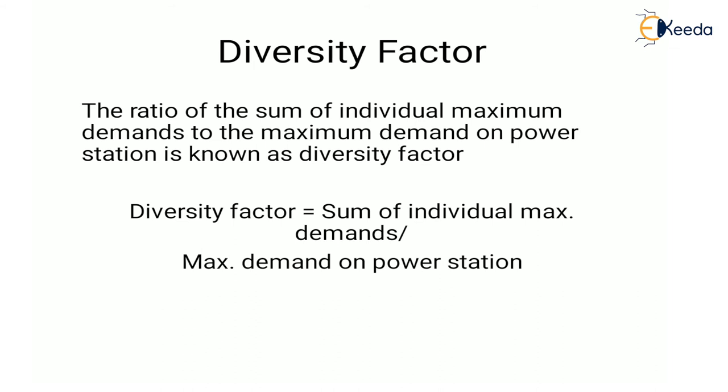Next is diversity factor. It is the ratio of sum of individual maximum demands to the maximum demand on the power station. The effect of diversity factor is to reduce the simultaneous maximum demand on the station for the same individual demands. This also reduces capital cost for the station and consequently a lower overall rate for generation of electricity. The higher the value of load factor and diversity factor, the lower will be the overall cost per unit generated. The supplier should always try to improve the load factor as well as diversity factor by inducing consumers to use electricity during off-peak hours, and they may be charged at a lower rate for such schemes.